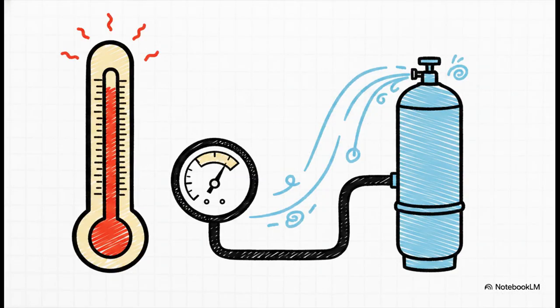If you guessed underfilled, you hit the nail on the head. Remember, 2.5 bar is only the correct target if the room is sitting at a comfy 20 degrees Celsius. Because it's a hot 30 degrees, the gas should naturally be exerting 2.6 bar of pressure. So, signing off on a 2.5 bar reading at 30 degrees means your gas density is dangerously low, and that breaker needs topping up with SF6 before you can even think about calling it sea-ready.